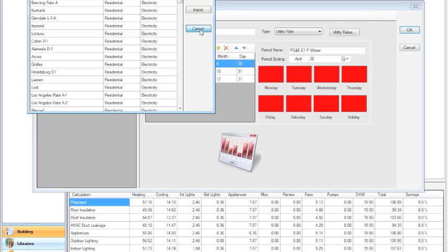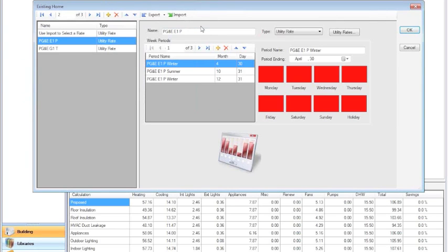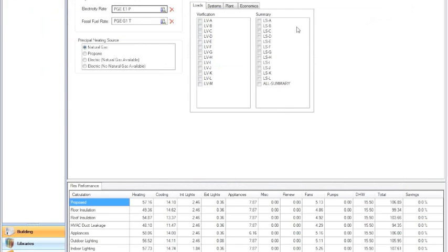Okay, thank you. The next question that was posted, and I'm going to try and put these answers in there as you get to them: Do you deduct the glazing from the wall area? You already answered that, actually, that EnergyPro automatically deducts the glazing area from the wall area as you enter it. Anytime you put in the wall area and the roof area, always put in the gross area, and the software will automatically do the deduction for you.